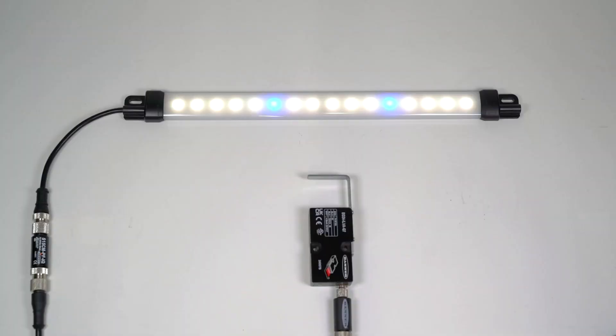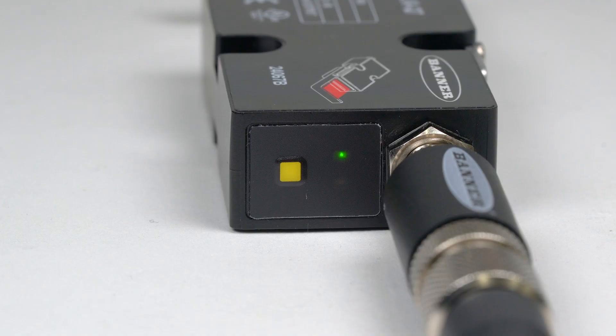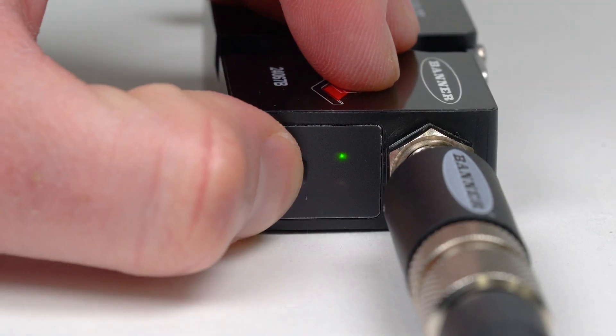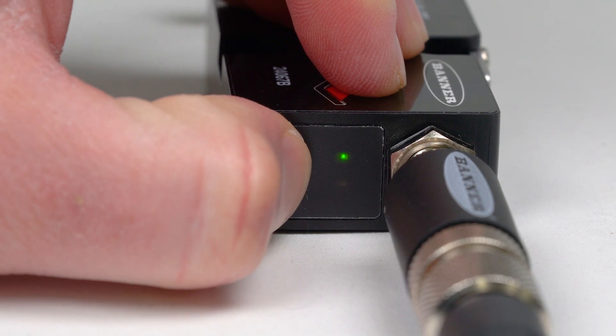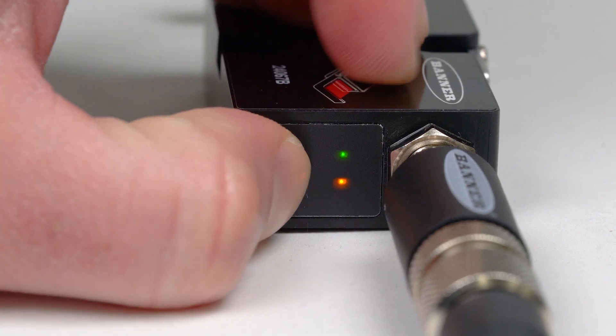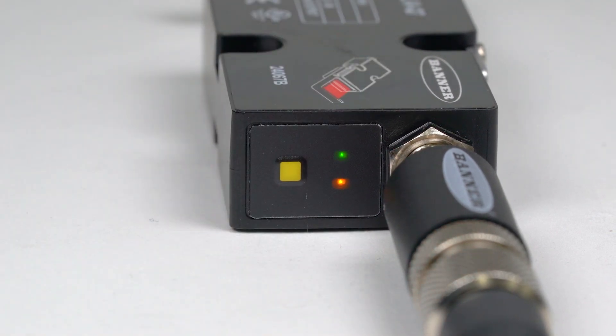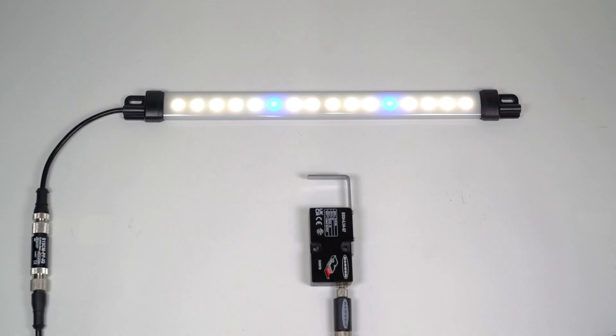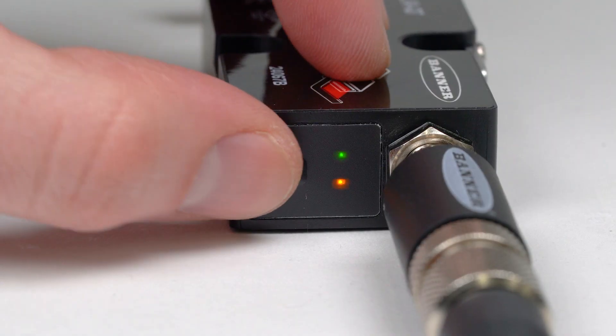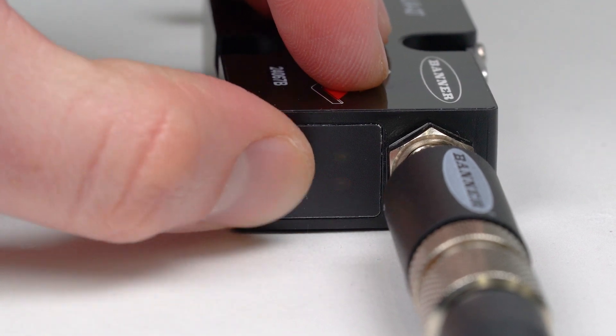To set the sensor to utilize the full field of view, begin by pressing and holding the button on the back of the housing for two or more seconds. The LEDs will begin flashing in unison to indicate that the sensor is in teach mode. Ensure that the beam is completely unobstructed and press the button one time.